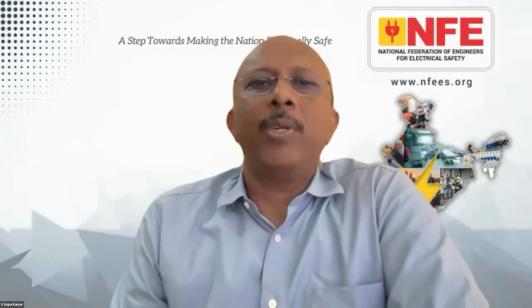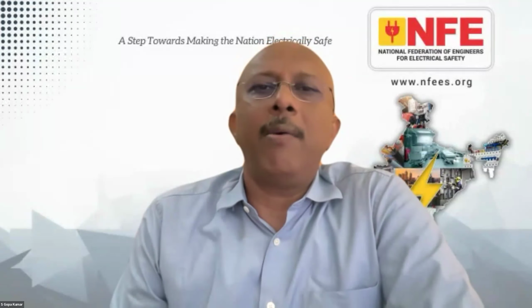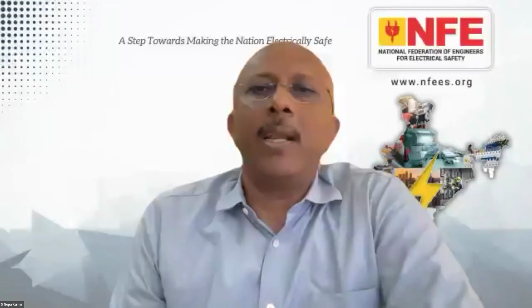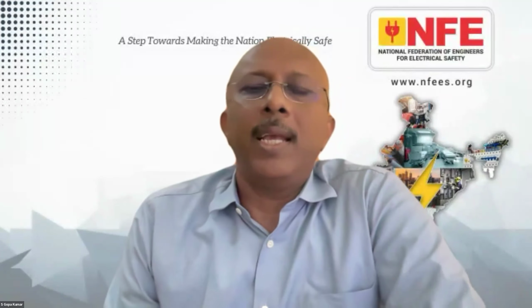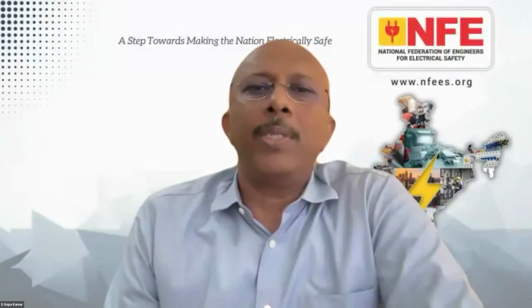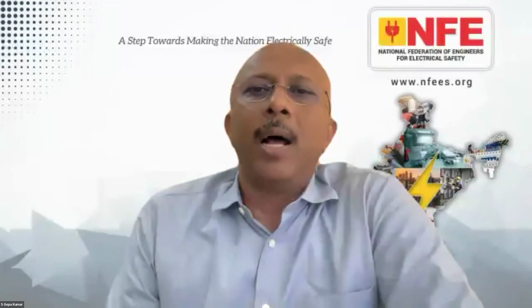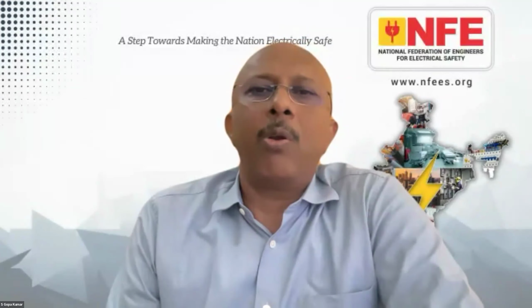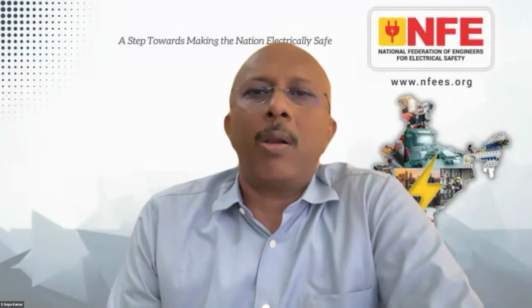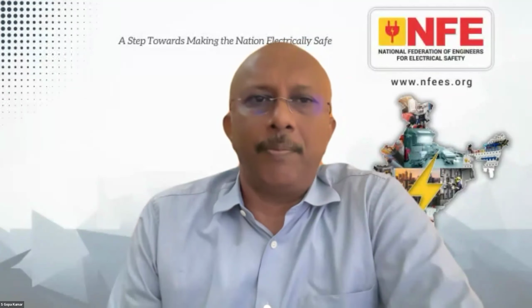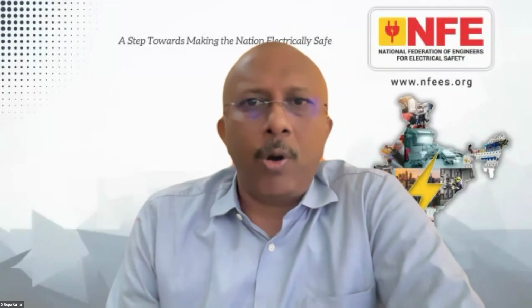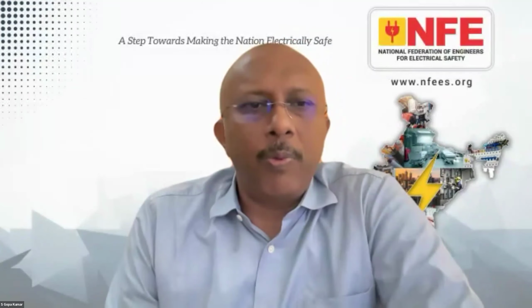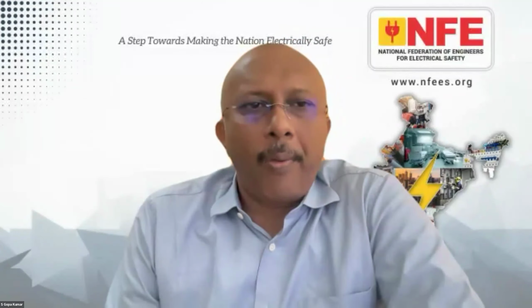Yes, Krish, the first question. Mr. Abhijit says: I have multiple installations from the 90s where we have voltage-based ELCBs installed. Every time they try to measure fault loop impedance, they trip. Is fault loop impedance relevant for this product? Is the tripping normal, or is something wrong with the system? Meaning, for a voltage operated ELCB, does the fault loop impedance test work? Yeah, okay. May I answer? Yes. So I'll just share the screen again.